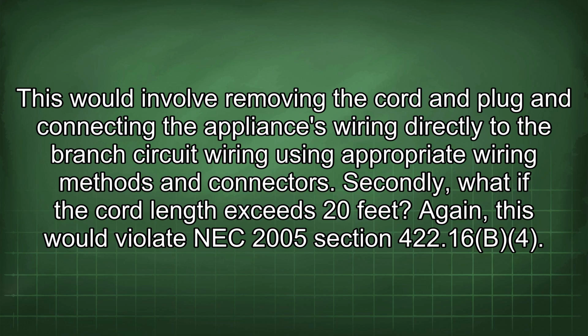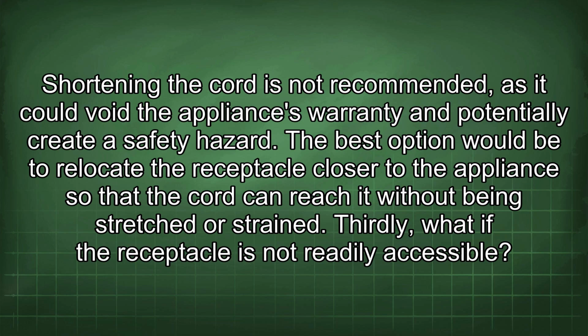Secondly, what if the cord length exceeds 20 feet? Again, this would violate NEC 2005 Section 422.16(B)(4). Shortening the cord is not recommended, as it could void the appliance's warranty and potentially create a safety hazard. The best option would be to relocate the receptacle closer to the appliance so that the cord can reach it without being stretched or strained.